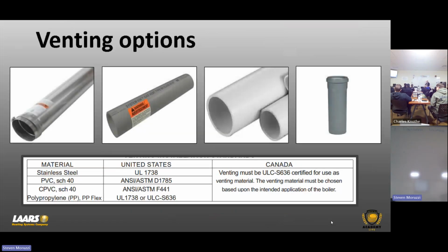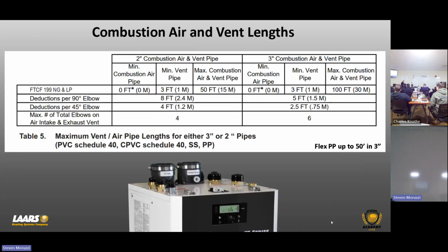Venting options here. So we are certified for all the vent material, but keep in mind, you guys are only certified here on your exhaust for polypropylene. Okay. No PVC, no CPVC. Combustion air intake, I think you could use cardboard if you wanted to. So combustion air intake doesn't matter, but your exhaust obviously does. Okay. You are limited to some fittings here.